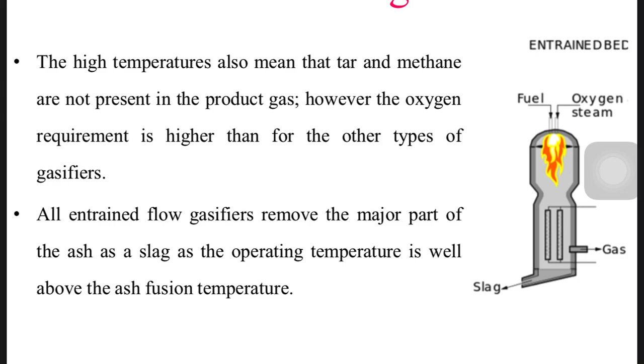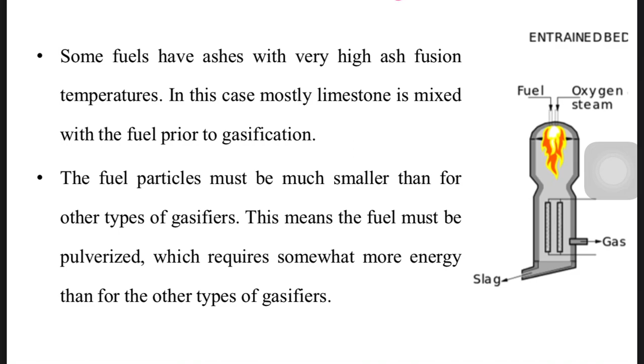In a particular case, biomass slag can be corrosive for the ceramic inner wall. However, entrained flow types of gasification do not possess a ceramic inner wall, but have a cooled wall facility, so they do not suffer from corrosive slag. That is the advantage of that. Some of the fuel has ashes with high fusion temperatures. The fuel particles must be much smaller than in the other gasifications. This means the fuel must be pulverized, which requires more energy than the other gasifications. That is another disadvantage of that.